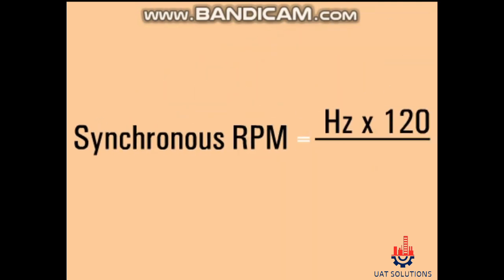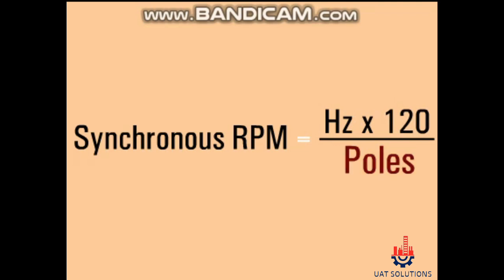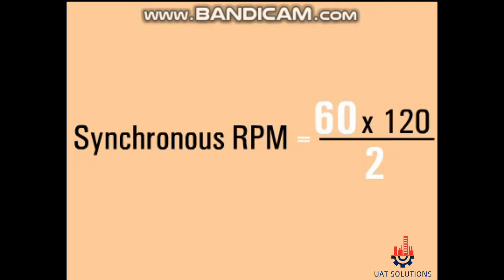The synchronous RPM formula shows that the motor speed is directly proportional to the applied frequency and inversely proportional to the number of poles in the motor. Therefore, a two-pole induction motor running at 60 hertz will run at 3600 RPM synchronous speed, less the slip required to produce the induction effect at full load.